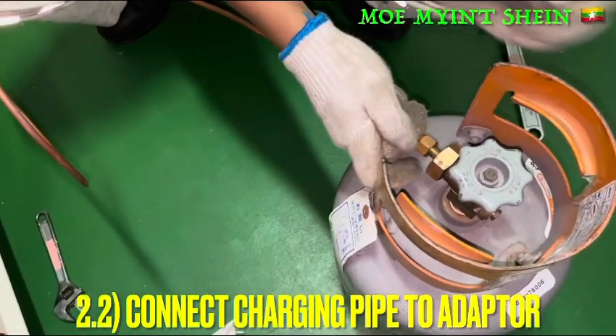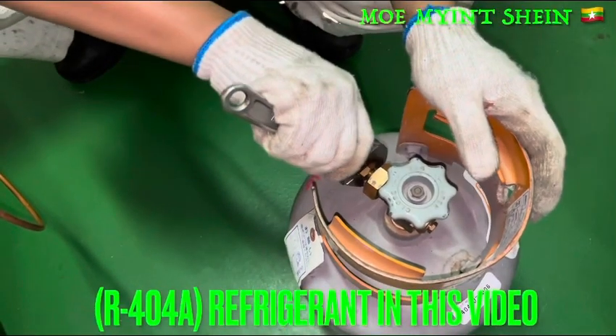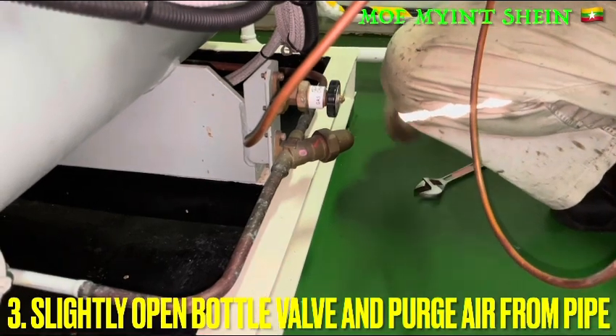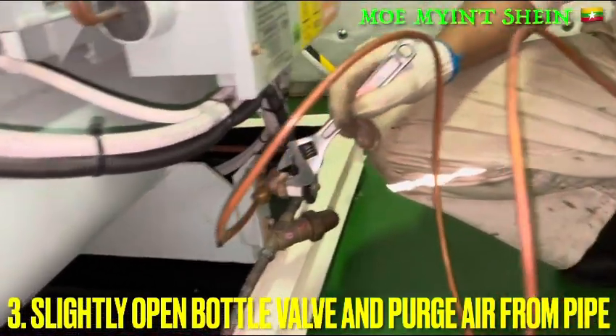We need to make the loose connection between the charging pipe and the liquid charging valve to push off the air from the charging pipe. For passing the air from the charging pipe, small open the bottle valve. If the gas comes out from the loose joint, we need to tighten the joint.